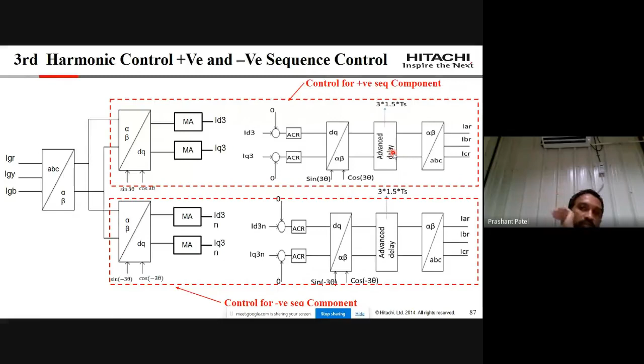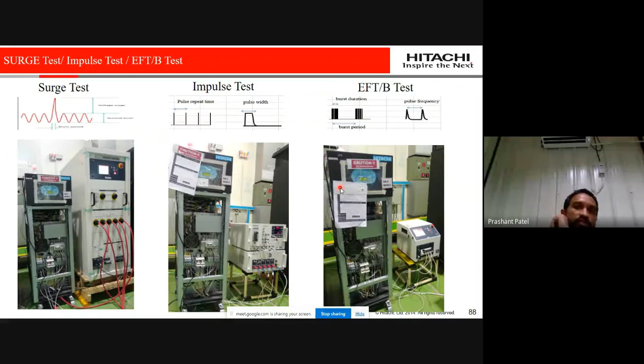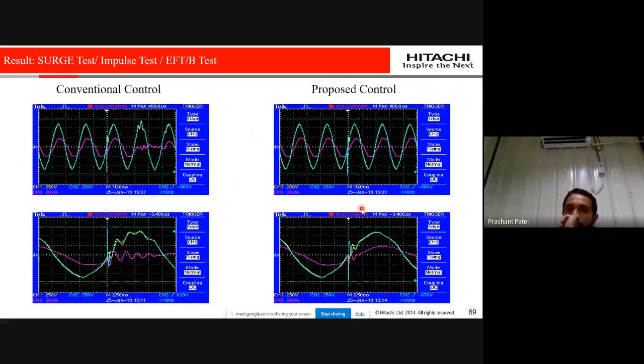After this, we are also doing these three tests. We are giving some surge tests in the grid. We are applying impulses in the grid voltage. It is a fast transient we give in the grid, and we test whether our converter is able to maintain synchronism and connect with the grid or not. All these conditions we have verified in our factory premises. With this conventional control, if we give a transient or impulse here, it fails. If we give a surge here, it fails. But now with this modified and robust control, it's functioning very fine. There should not be any problem.